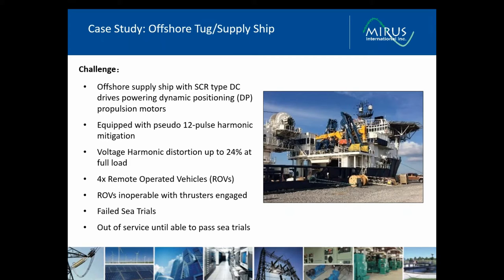I'll start into some of our case studies, examples of where harmonic mitigation was applied in various marine and offshore applications. This first one is a vessel that was equipped with DC propulsion drives, and it was purchased to be modified, retrofitted, and upgraded for use as a supply and service vessel for the offshore oil and gas industry. However, due to multiple failures caused by high harmonic voltage distortion, it could not pass sea trials. Problems included loss of navigation and operational issues, such as component failures in crane controls and remote operated vehicles, which occurred particularly during dynamic positioning operation, when the voltage distortion reached levels above 24%, which is extremely high, and of course, equipment is likely to have problems at those levels.